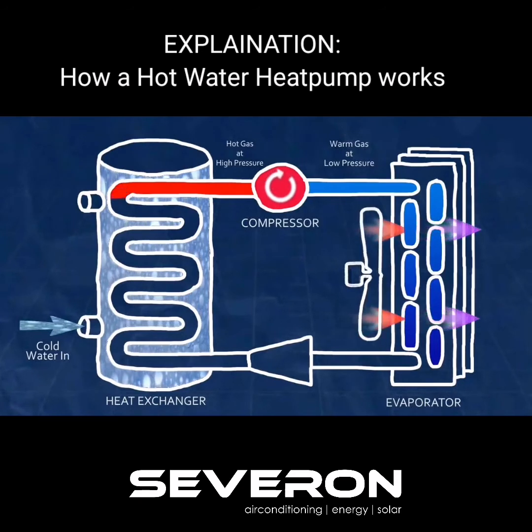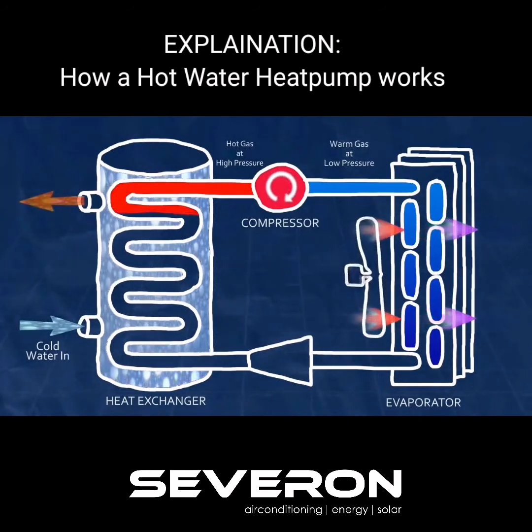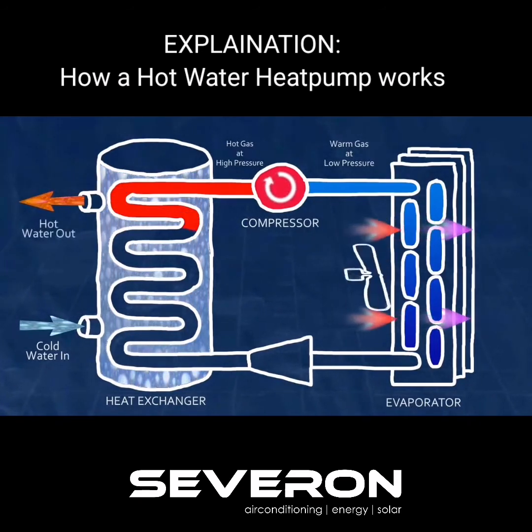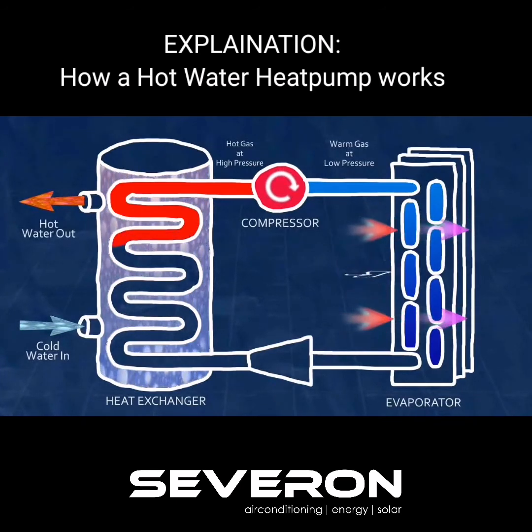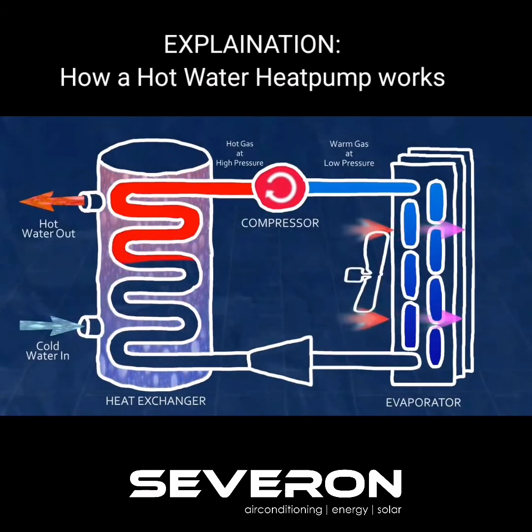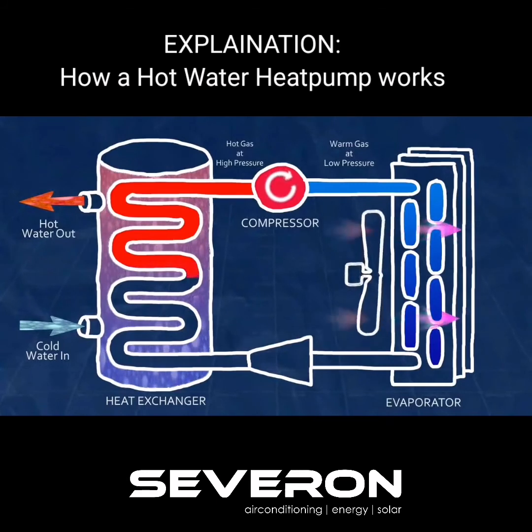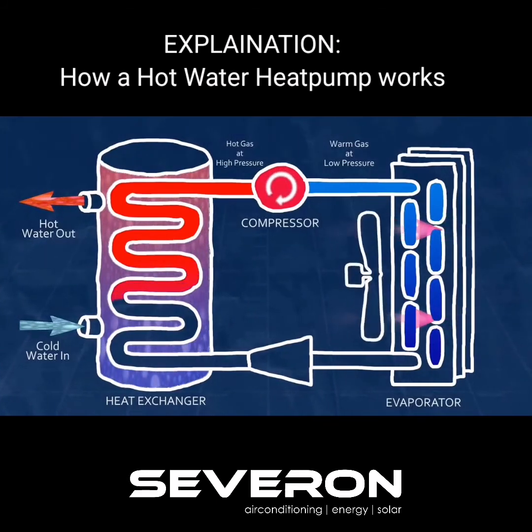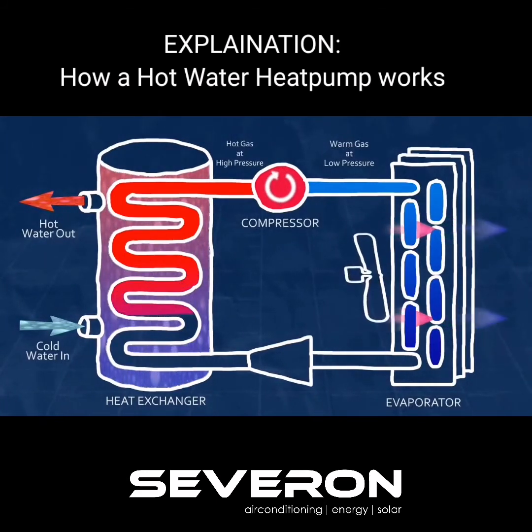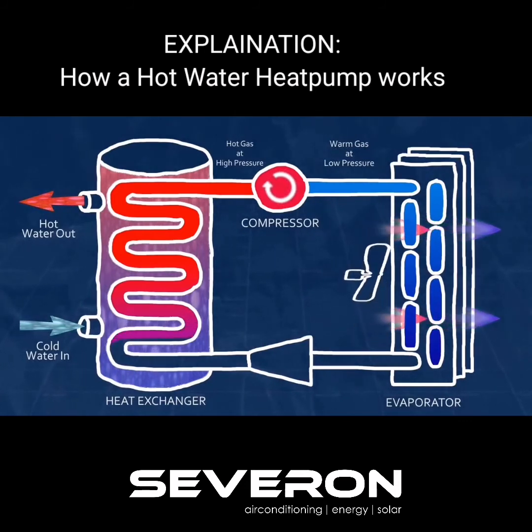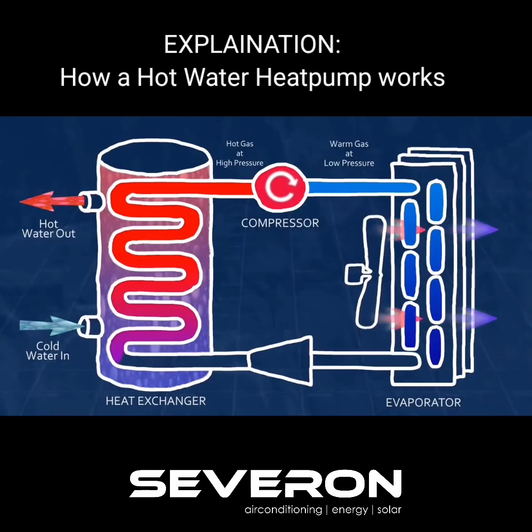The condenser is in contact with the water, and the hot gas now gives up its heat to the colder water. As heat leaves the gas refrigerant, it cools off below its condensation point and changes from a gaseous state to a high-pressure liquid state. The change from gas to liquid facilitates the large transfer of heat energy to the water.